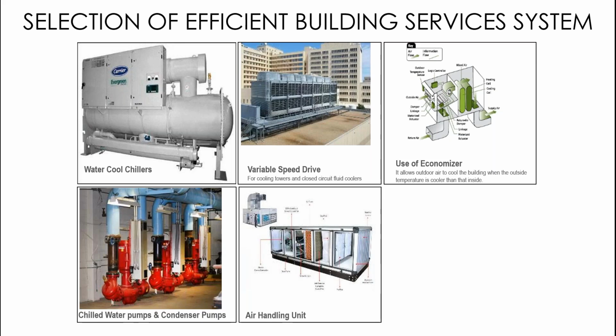But here we removed the secondary pumps. We used primary pumps for both the chiller section as well as the building load, something called primary variable, which we have now been using in a number of buildings. This helped me reduce the number of pumps, and it also helped me reduce the installed kilowatts of the plant.